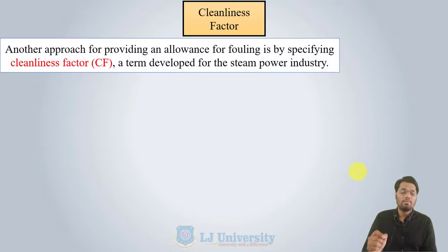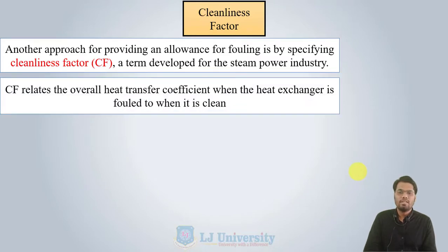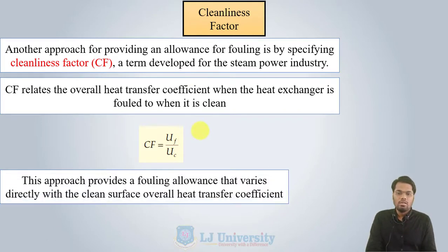The second factor which we need to define is the cleanliness factor, denoted by CF, a term developed by the steam power industries. The CF relates the overall heat transfer coefficient when the heat exchanger is fouled to when it is clean. It is generally the ratio of the overall heat transfer coefficient of the fouled surface to that of the clean surface.